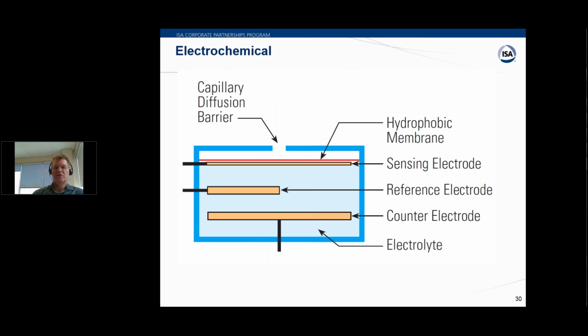This one should look familiar to all of you. This is the electrochemical cell. A little bit like pH, right? There's our sensing electrode, our electrolyte, and our reference electrode. And typically we'll have a hydrophobic membrane just to protect it from water. And then we have a diffusion barrier where the gas comes through. Some alternate names for electrochemical are amperometric or microfuel cell.